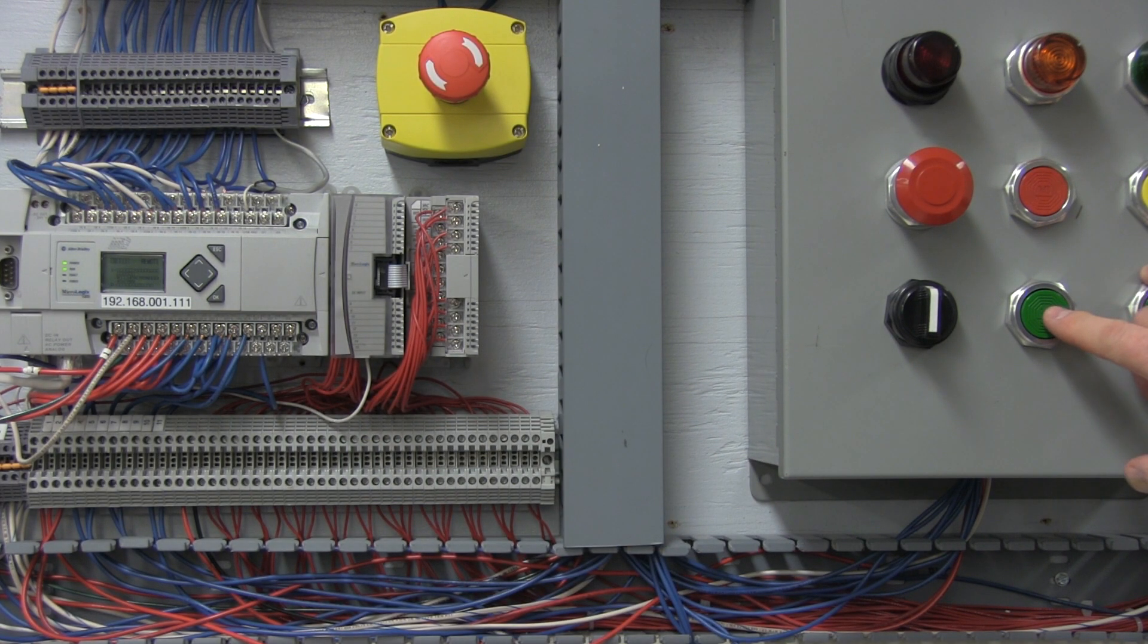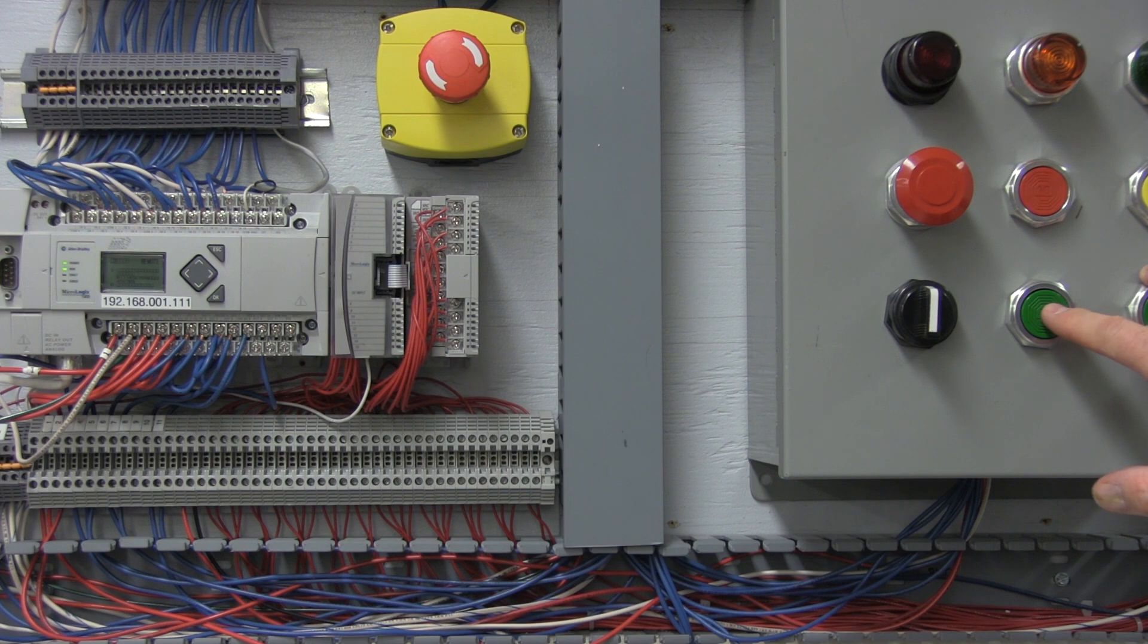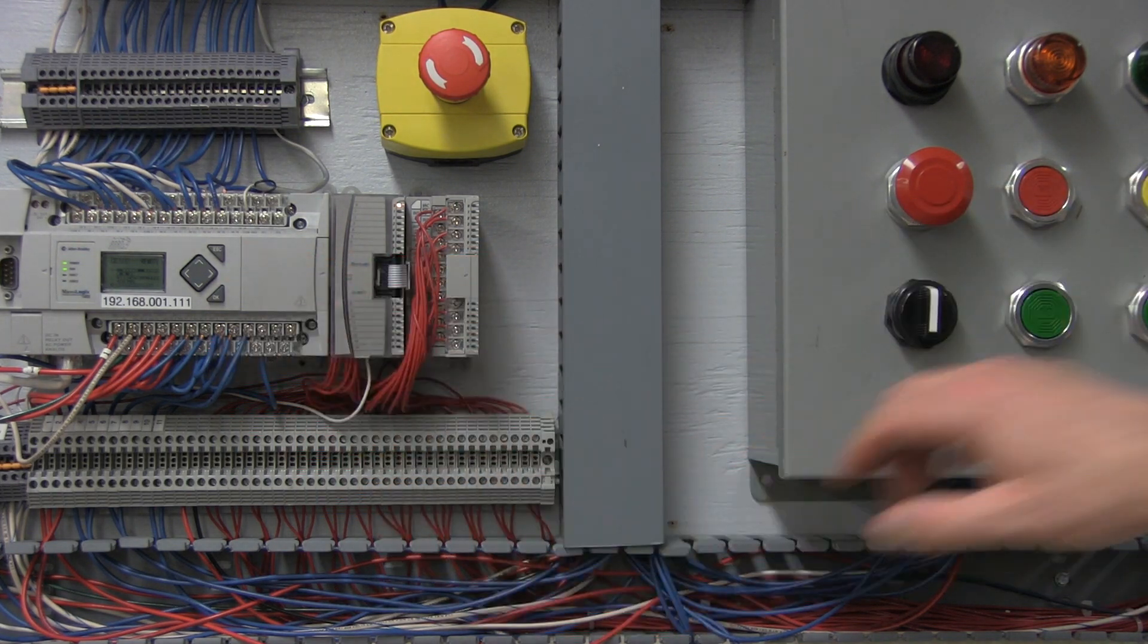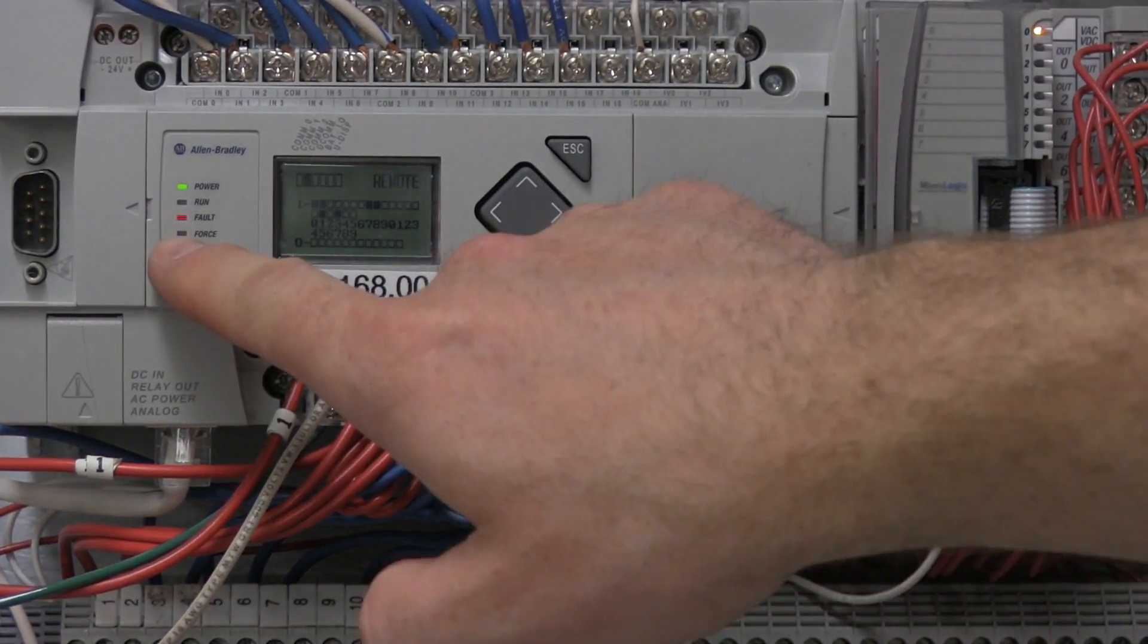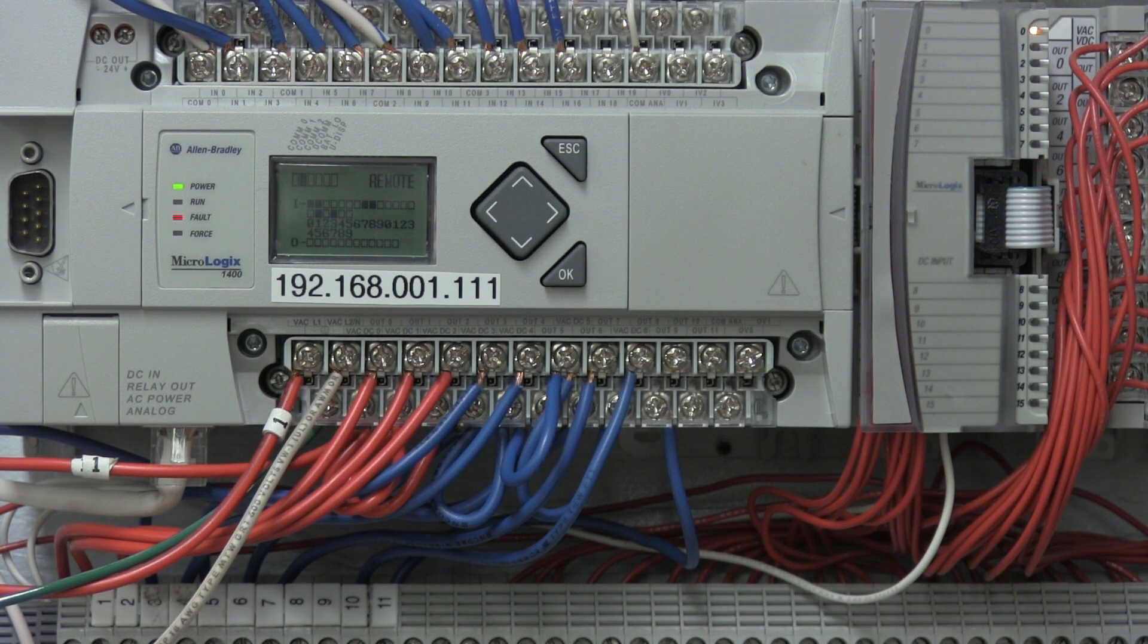How we go through the steps of identifying and hooking up to that PLC and finding the fault. So when I push this button here, this PLC will fault out and then we will walk through the steps of what we do in RSLogix 500 to hook back up to it. So this is the MicroLogix 1400. When I hit this button, the PLC will fault out. You can see right here that the PLC is now faulted out. It has shut off all outputs and nothing will operate. So now I'm going to go to RSLogix 500 and I'm going to walk you through how we fix that.